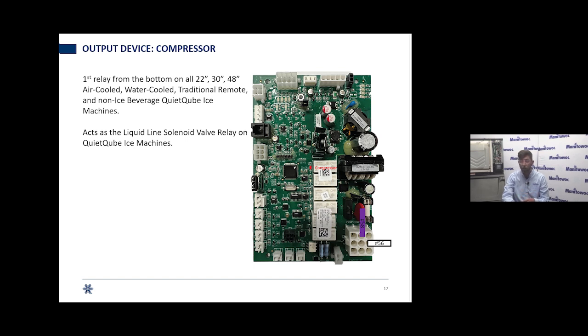So what you'd want to do at that point is look at your wiring diagram and find the wires you would be checking across. You could do this at the board or at the component. If you check across the contactor coil and you don't have power, well, you could also check at the board at wire number 58, and 56 is going to be common to all of your outputs. It's the L2 line coming into the board. So 56, 1 meter lead against it, 58, 1 meter lead up against it. On a 115 volt machine, you should see 115. On 208, 230, same should be true, you should see 208, 230.